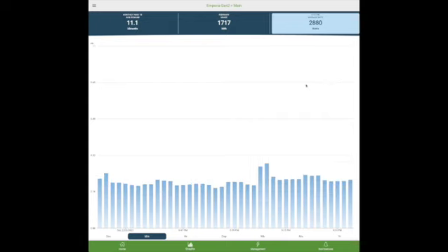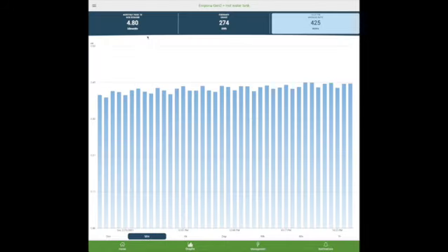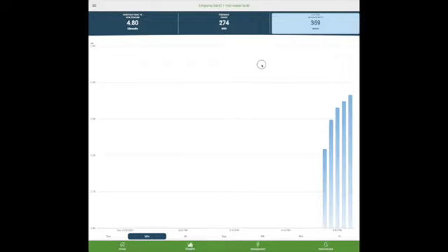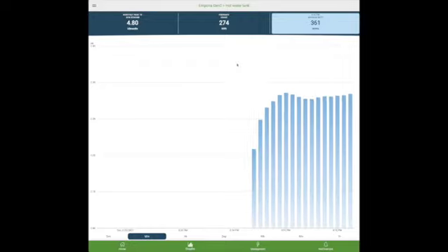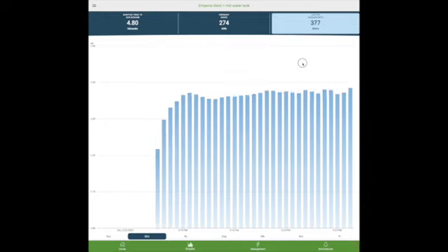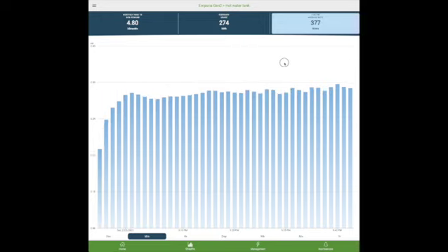That tells me my hot water tank is running in that time frame. So I clicked on hot water tank. What did I say, 9? Ooh, too far, go back. So my hot water tank wasn't on right here. It kicked on at 9 something. There it is, it kicked on. It was running the hybrid pump, the heat pump, at this time right here. And oh, something else is pulling 3,000 watts.